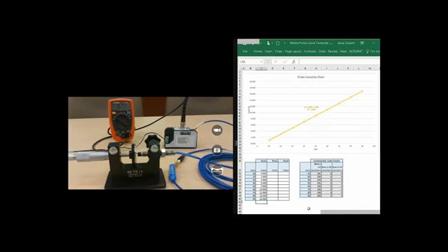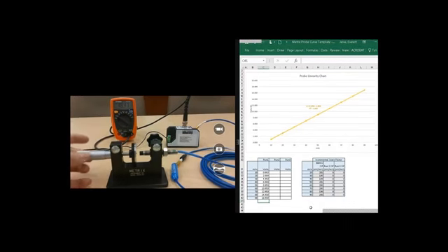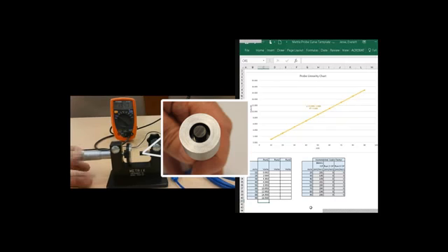We'll now add a carbon steel fixture that will impact the proximity probe readings. The normal counterbore for a proximity probe is at least one probe tip diameter, which is represented by the outside diameter of the steel fixture. The probe will occupy the hole in the middle. However, to force a tight view situation, we are going to use a 0.5 inch or 12.7 millimeter counterbore. You can see the 8 millimeter probe has a very tight side clearance.